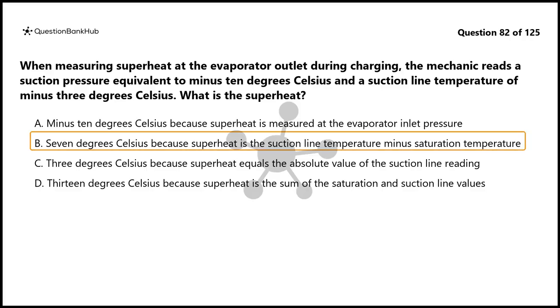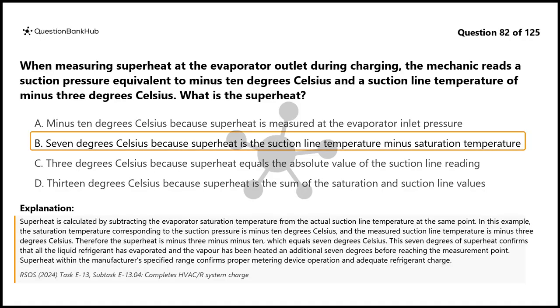The correct answer is B. Superheat is calculated by subtracting the evaporator saturation temperature from the actual suction line temperature at the same point. In this example, the saturation temperature corresponding to the suction pressure is -10 degrees Celsius, and the measured suction line temperature is -3 degrees Celsius. Therefore the superheat is -3 minus -10, which equals 7 degrees Celsius.